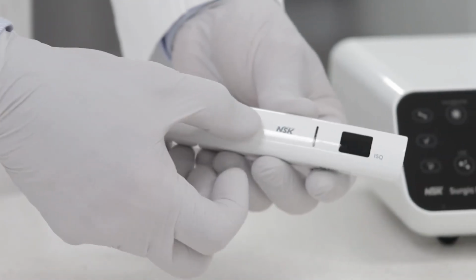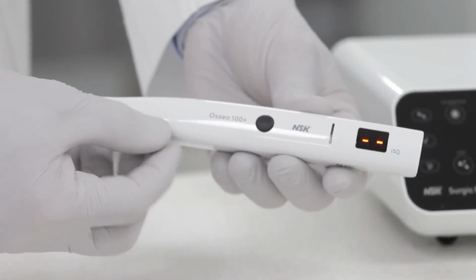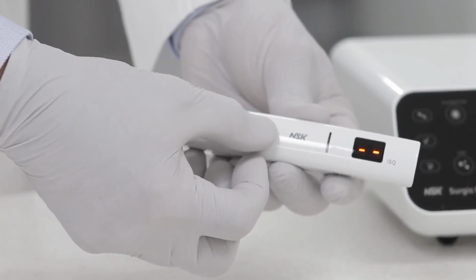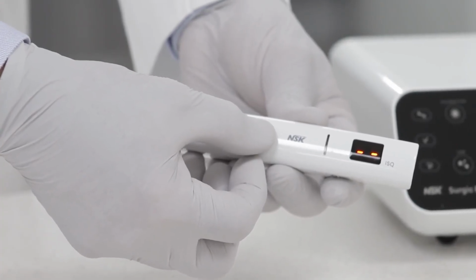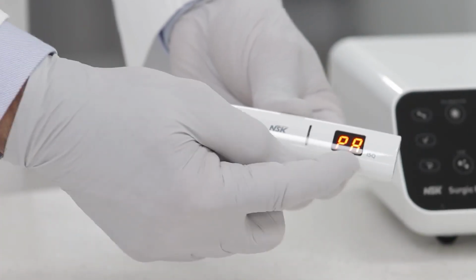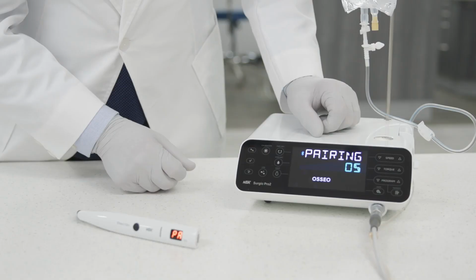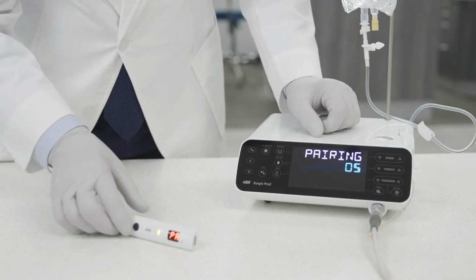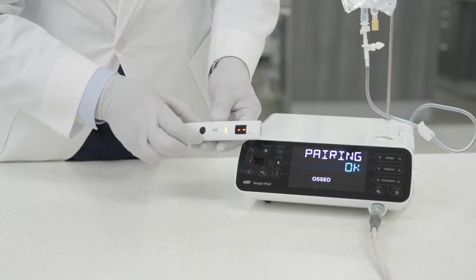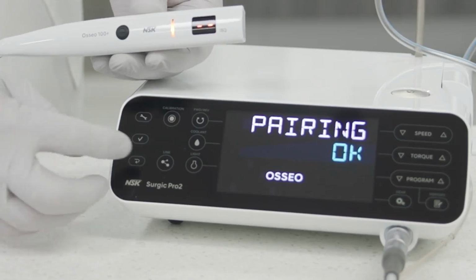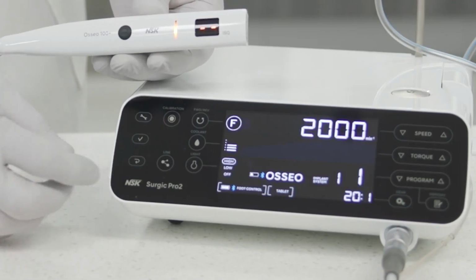On the Osseo 100 Plus, press the operating key to turn it on with a beep. Press and hold that key again for 3 seconds to enter its pairing mode. PA is displayed. Now, hold it near the SurgicPro2. In a few seconds, the 2 units will pair and OK will be shown on the display of the SurgicPro2. Press Return twice to go back to the main screen.